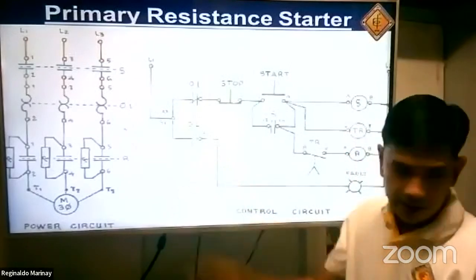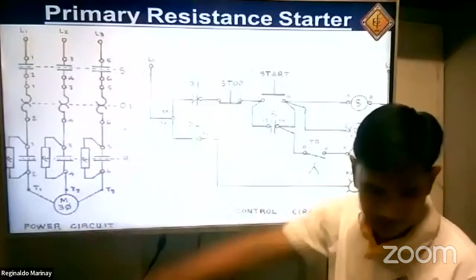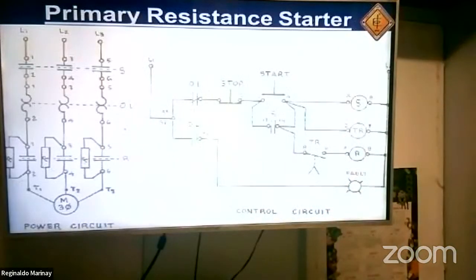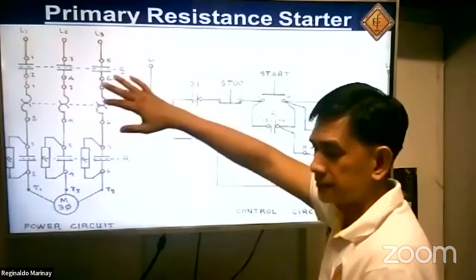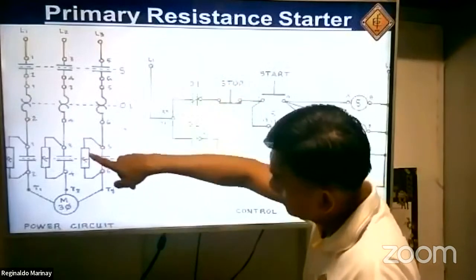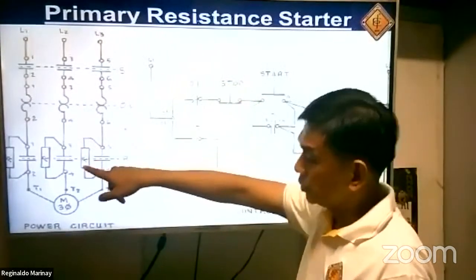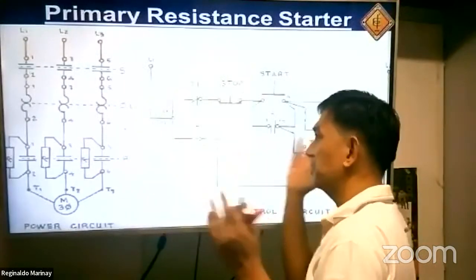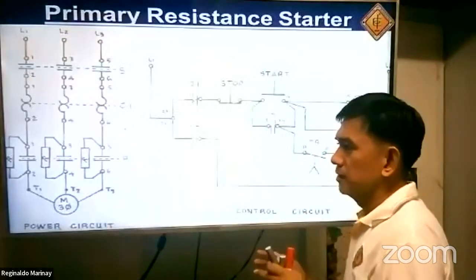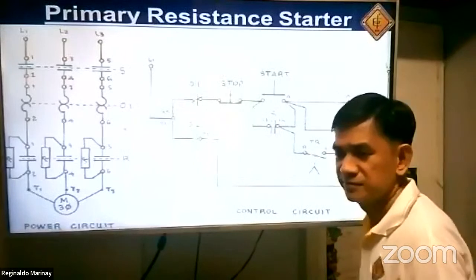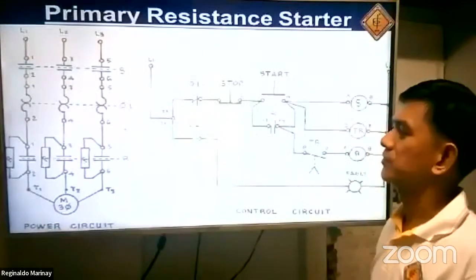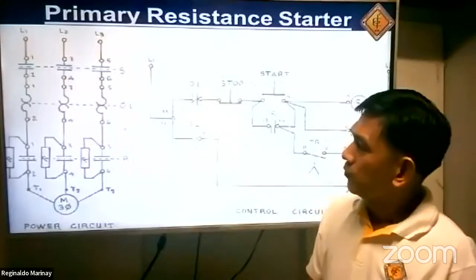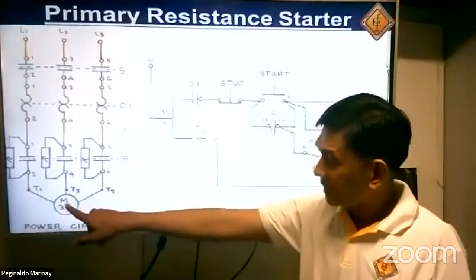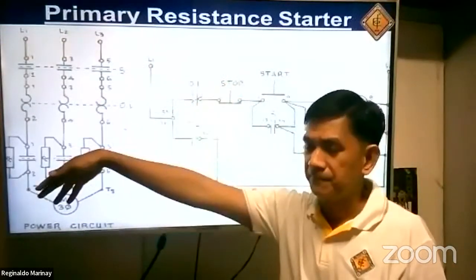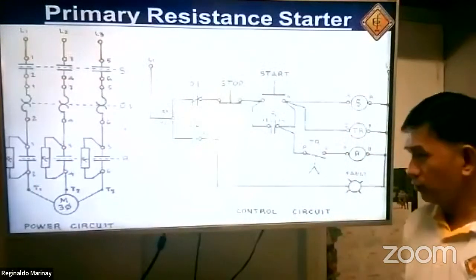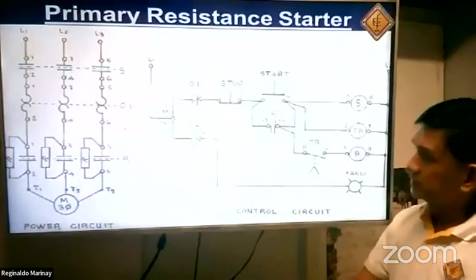So, with the resistance unit, let's say you set your timing relay for 3 seconds, you will just use this for around 3 seconds, to protect your motor. Because your motor may be damaged once you impress directly all the full voltage. This may damage it. Okay? That's why you need to put the resistance units.